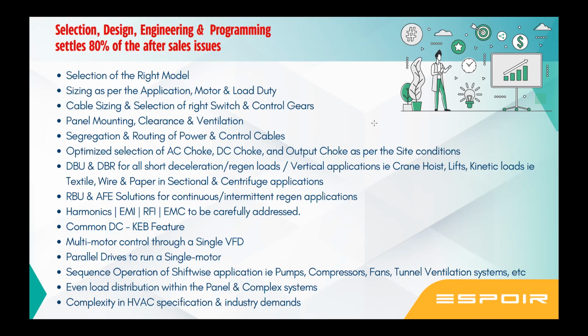So you need to select and size an OLR as per the particular motor on the output of a VFD. You connect 1 HP, 2 HP, 3 HP motors on a 10 HP drive. So the 1 HP motor should have a 1 HP OLR, the 3 HP motor should have a 3 HP OLR. It's as simple as that. But all motor outputs should be connected before you give the run command, so that the start-stop pattern, acceleration and deceleration happen smoothly. Otherwise, if you switch on the motor after the VFD is already on and the acceleration is over, it is going to work as a DOL because it has already achieved its full frequency. If you switch on the output contactor after the acceleration is over, it will simply work as a DOL.